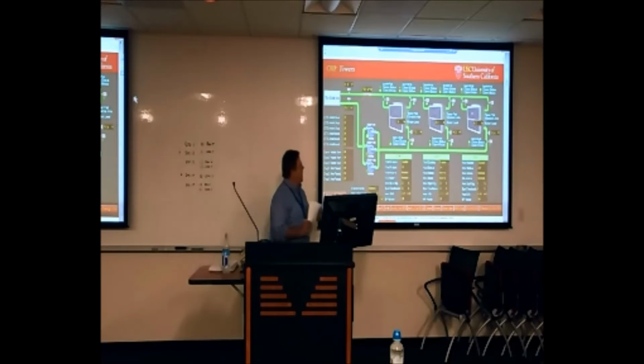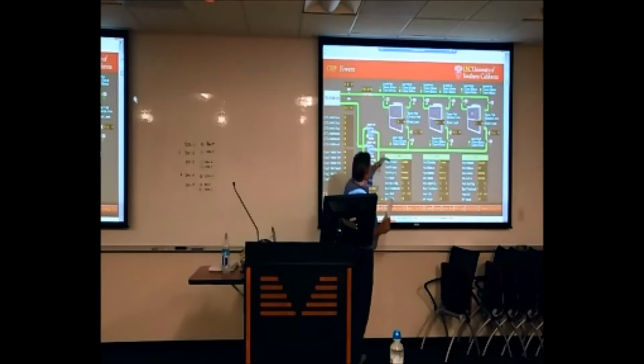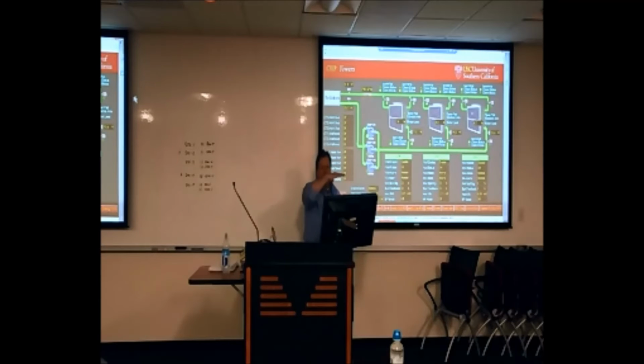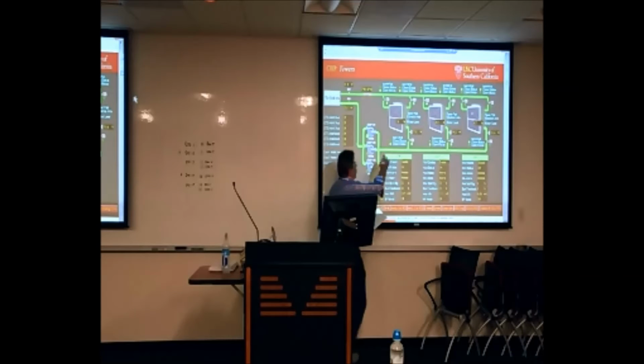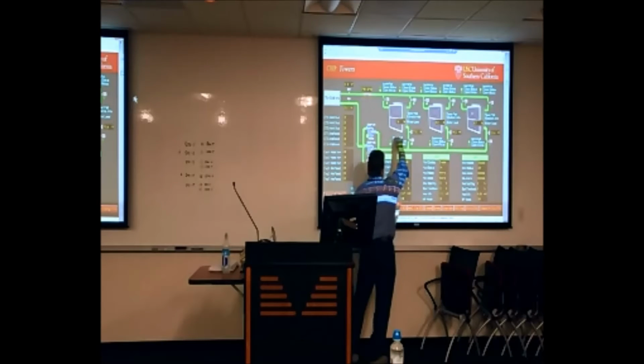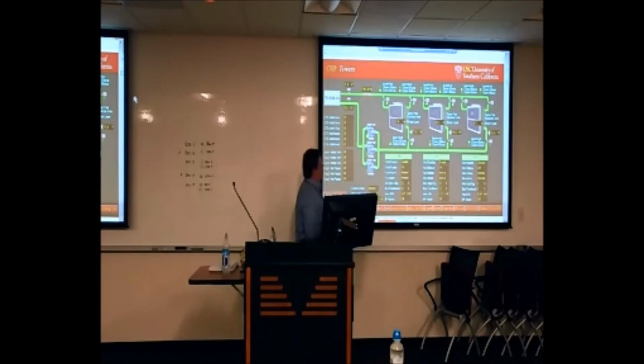Okay. And then if we only just go by virtue of where it's installed, we don't have much of a drop, and the tower is of a strange design in that it's got very little water in its sump. So I think if we're only just an inch or 2 below, no, not an inch or 2, but 2 or 3 inches below is where our low level alarm is going to be. It has a center trough, and then there's a higher section, only just an inch or 2 in it, and the bottom line is we don't have to go down too far before we're risking maybe sucking some air at the pipe. So the low limit happens quite quickly, maybe at about 3 or 4 inches or 2 or 3 inches.